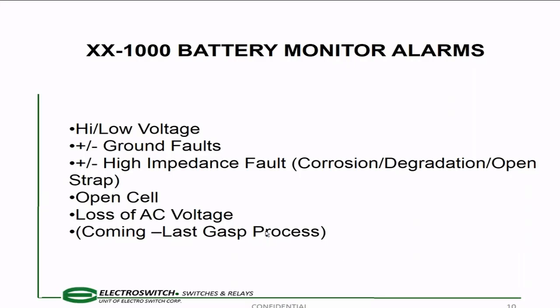This last gasp process I'll talk about later on. Actually, I can talk about it now. So you have a high-low voltage. A lot of times, if you have a 125-volt DC system, your high voltage is set at 142 volts and your low voltage is typically set at 105. Some people, instead of setting the low voltage at 105 volts, set it at 120 volts, and then 105 volts would be your last gasp. So we're looking at adding that feature. Our low voltage would be 120 volts instead of 105 volts, and 105 volts would be my last gasp, which means get out there and take care of your system because you're about to lose your battery and you're not going to have any control.